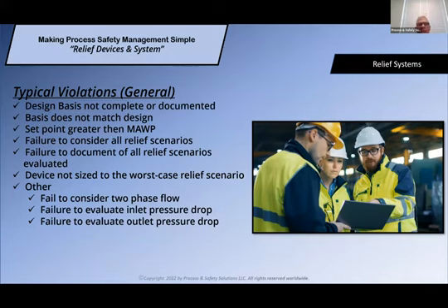So here are some typical violations that we see. Well, we've done many PSM compliance audits, and we look into relief systems. These are the most typical ones we see. And these are also the ones we see quite often that OSHA is citing.